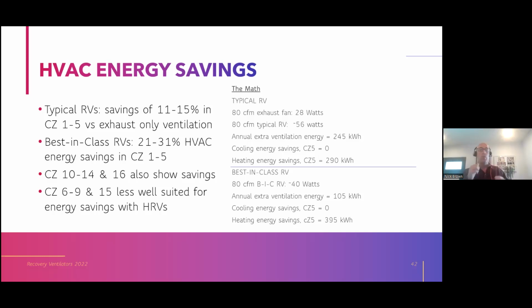Yeah. So we found typical recovery ventilators, that is not the best in class. These have watts per CFM in the 0.7 to 1 range. These have recovery effectiveness in the 70% range. We found energy savings of 11 to 15% in climate zones 1 to 5. So that covers most of 3C REN's territory, right? Which I would think of as 4 and 5 versus exhaust only ventilation.